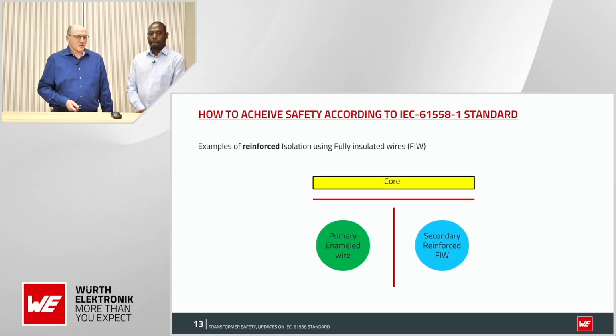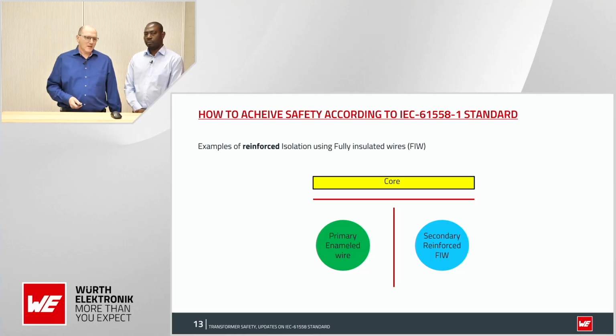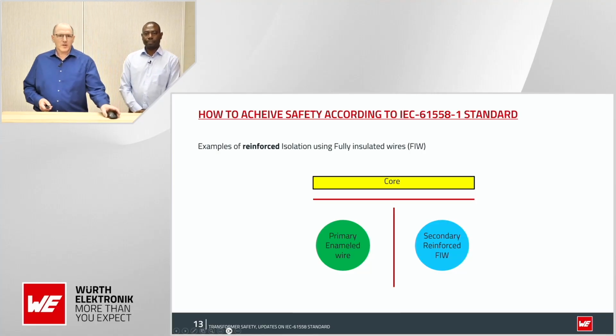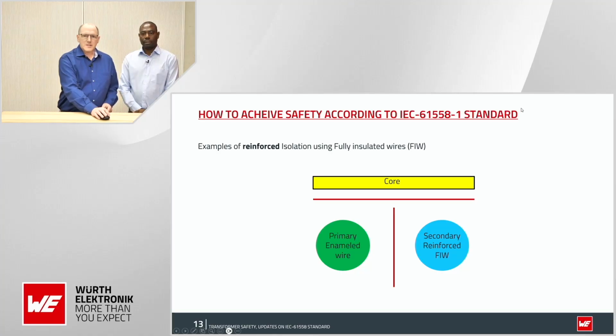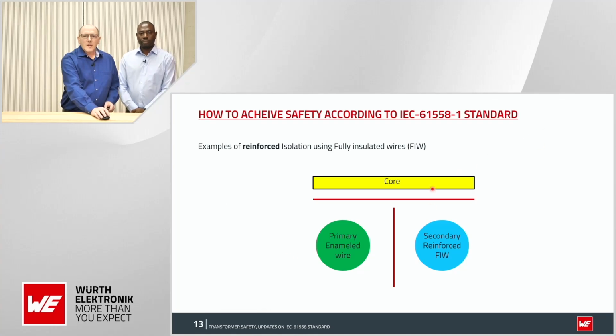And I will show you how to achieve safety according to IEC 61558. I have some examples of reinforced insulation using FIW, and we can see here the core, and the red lines here between the core and the windings, and between the windings themselves.